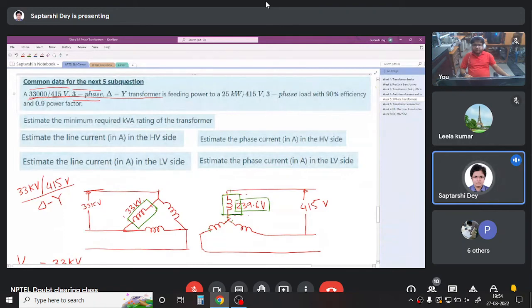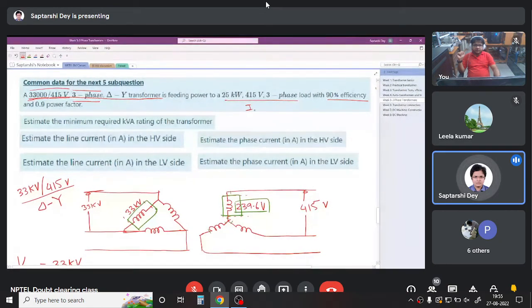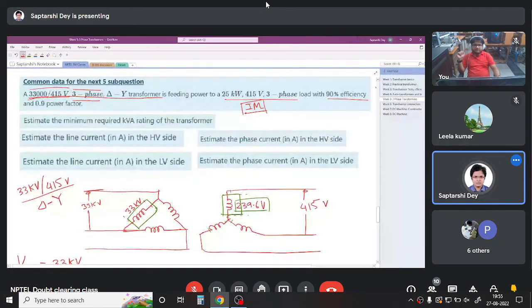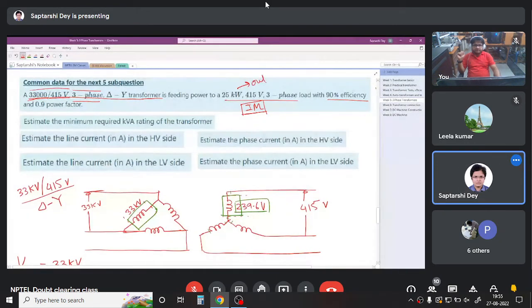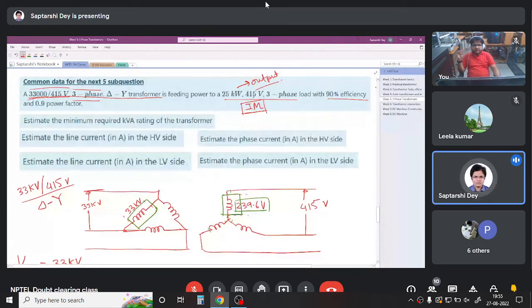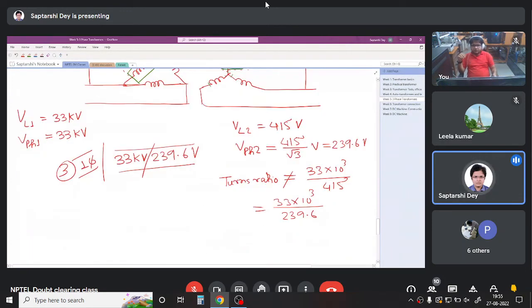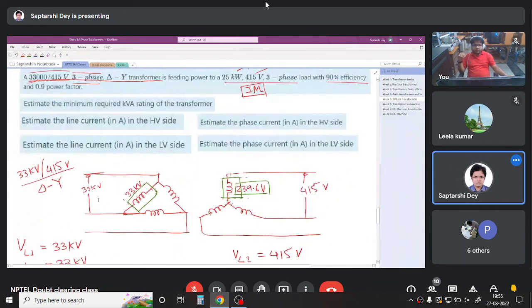The question says: 25 kilowatt, 415 volt, three-phase load with 90% efficiency and 0.9 power factor. Since they have mentioned the efficiency of the load, let us say it's an induction motor. When you have a motor whose power is mentioned in this fashion, that means this is the output power. Let me write it down once again: 25 kilowatt, 415 volt.